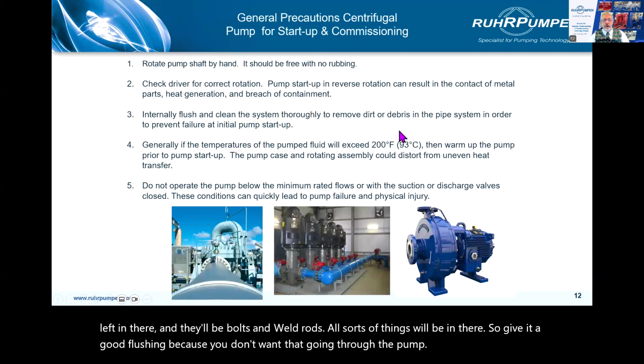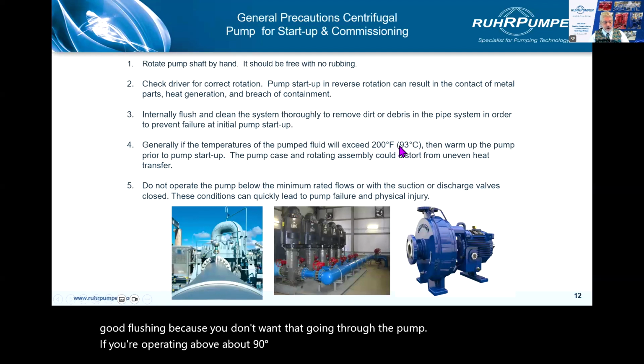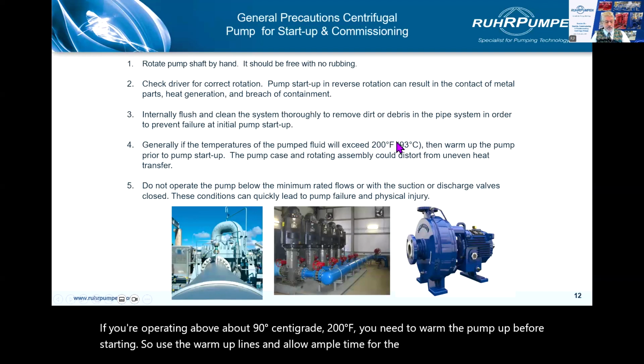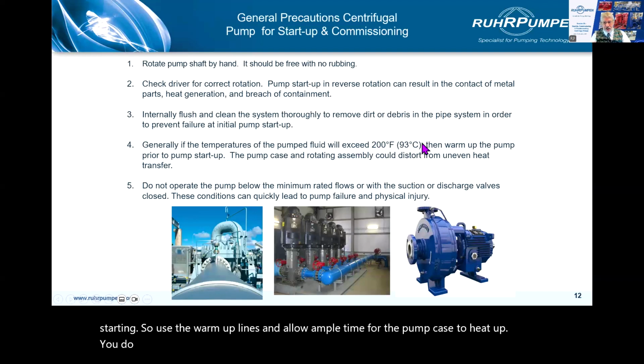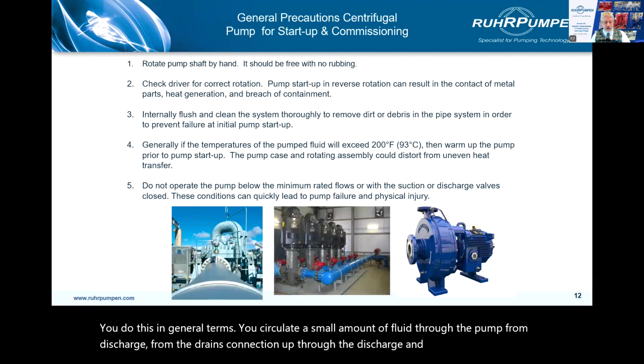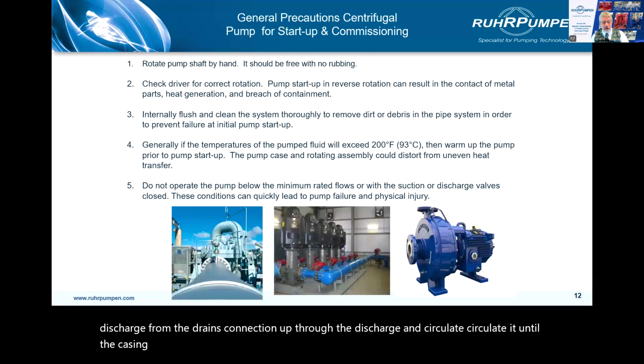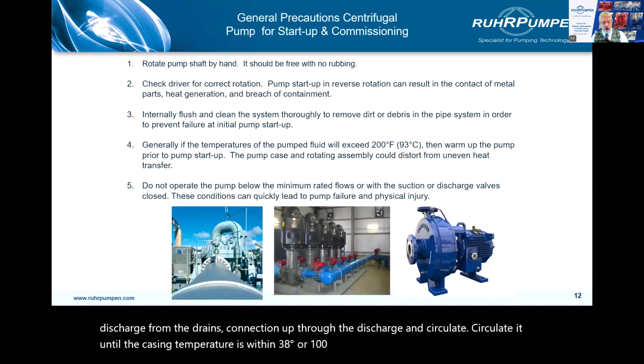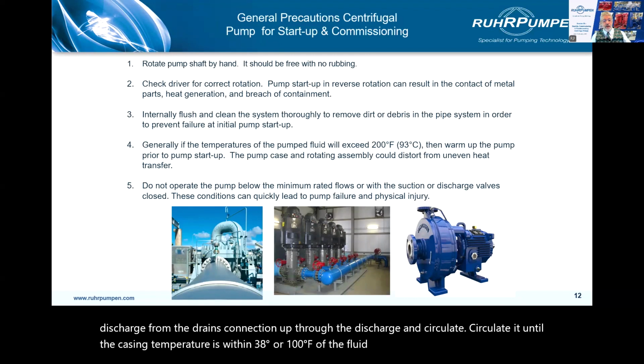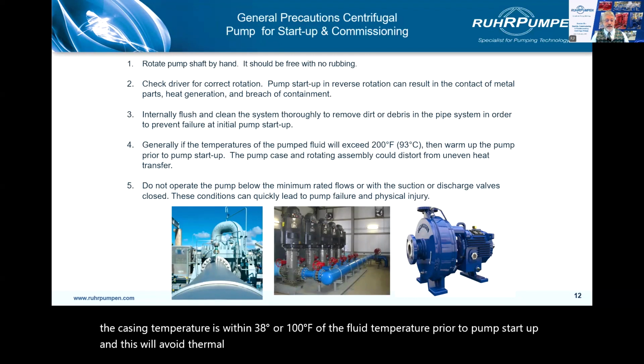If you're operating above about 90 degrees centigrade, 200 degrees Fahrenheit, you need to warm the pump up before starting. So use the warm-up lines and allow ample time for the pump case to heat up. You do this in general terms. You circulate a small amount of fluid through the pump from the drains connection up through the discharge, and circulate it until the casing temperature is within 38 degrees centigrade or 100 degrees Fahrenheit of the fluid temperature prior to pump startup. And this will avoid thermal shock to the casing and impeller and prevent damage of the mechanical seal.